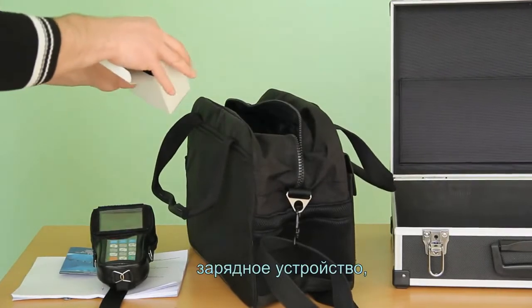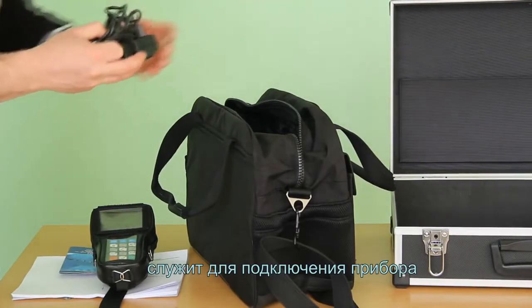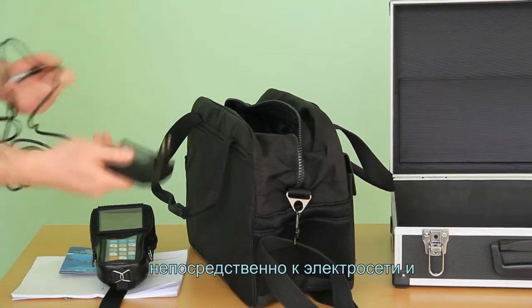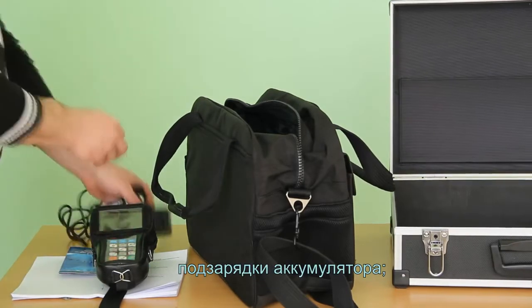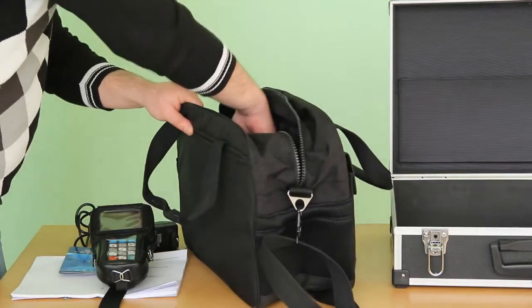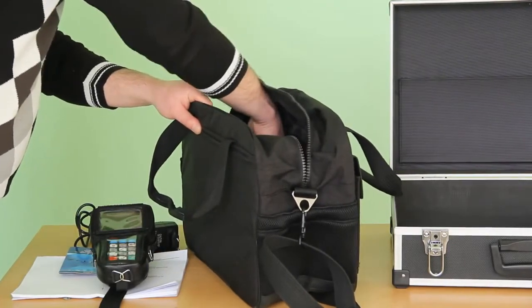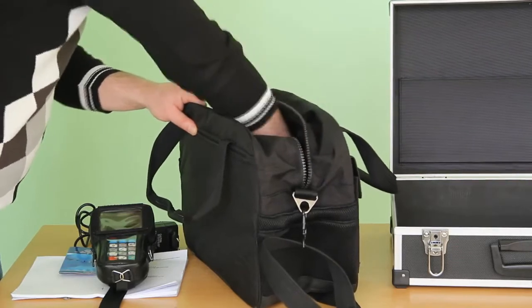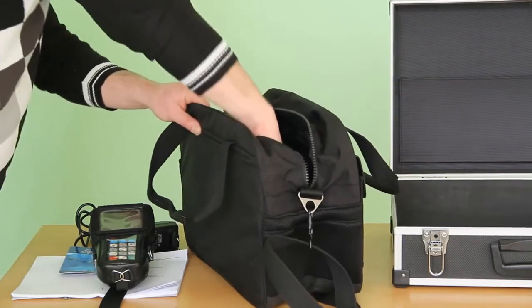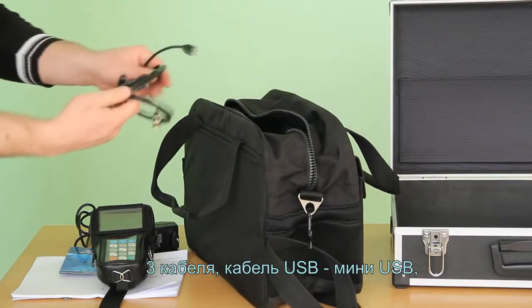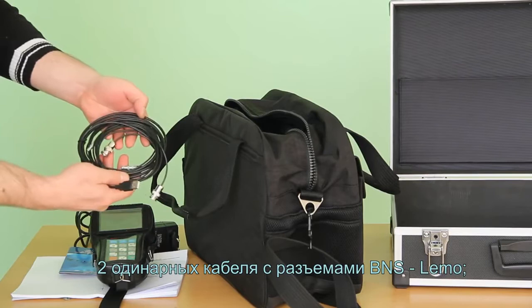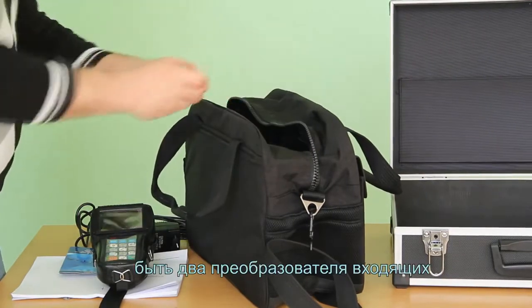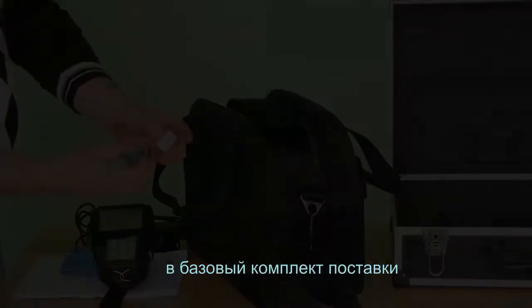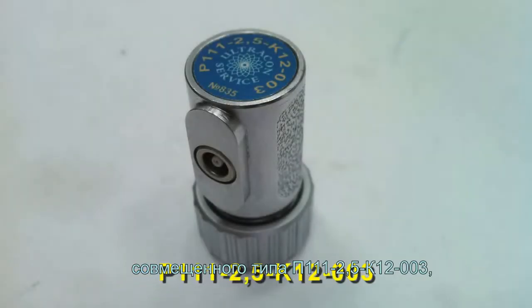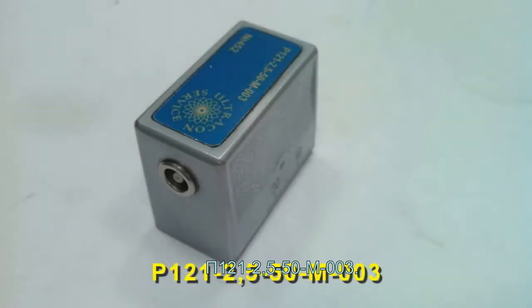Charger serves for connecting the flaw detector directly to the mains for charging the storage battery. Three cables: USB cable, mini USB, two similar cables with BNC LEMO. There should be two probes in a bag included in the basic delivery set: a straight beam piezoelectric transducer and an angle beam piezoelectric transducer.